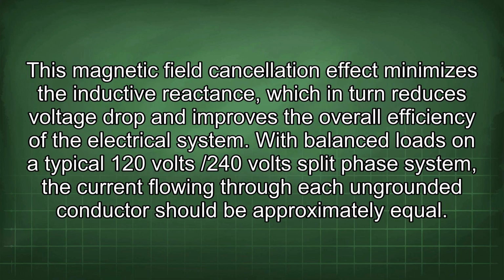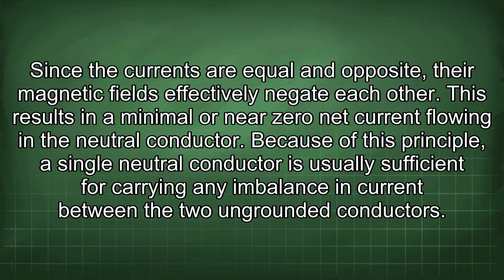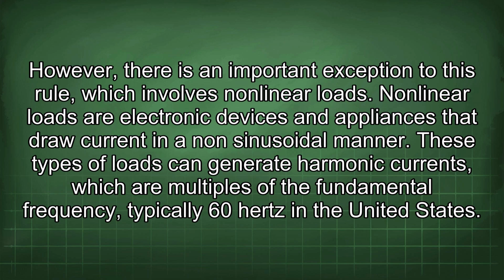This magnetic field cancellation effect minimizes the inductive reactance, which in turn reduces voltage drop and improves the overall efficiency of the electrical system. With balanced loads on a typical 120 volt/240 volt split-phase system, the current flowing through each ungrounded conductor should be approximately equal. Since the currents are equal and opposite, their magnetic fields effectively negate each other. This results in a minimal or near zero net current flowing in the neutral conductor. Because of this principle, a single neutral conductor is usually sufficient for carrying any imbalance in current between the two ungrounded conductors. However, there is an important exception to this rule, which involves nonlinear loads.